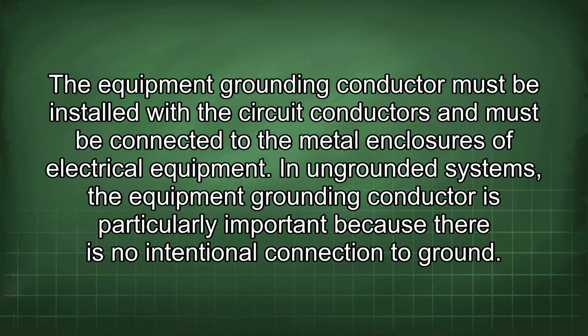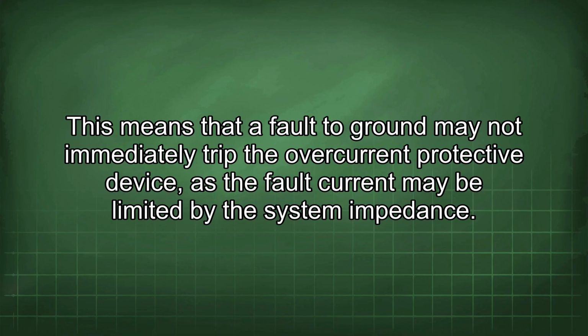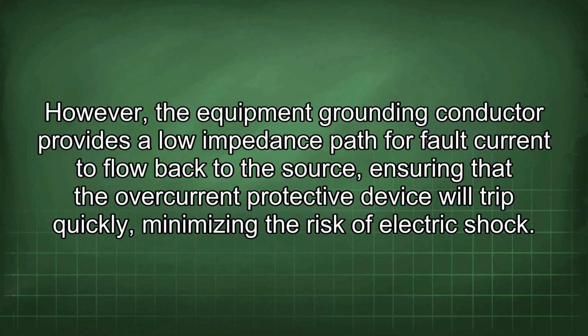electrical equipment. In ungrounded systems, the equipment grounding conductor is particularly important because there is no intentional connection to ground. This means that a fault to ground may not immediately trip the overcurrent protective device, as the fault current may be limited by the system impedance. However, the equipment grounding conductor provides a low impedance path for fault current to flow back to the source, ensuring that the overcurrent protective device will trip quickly, minimizing the risk of electric shock.